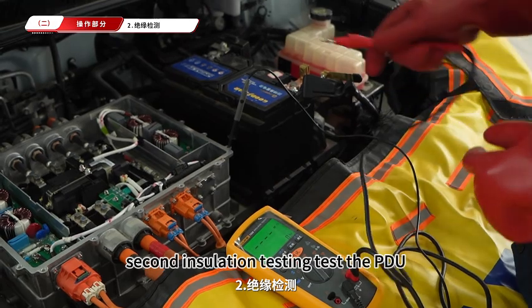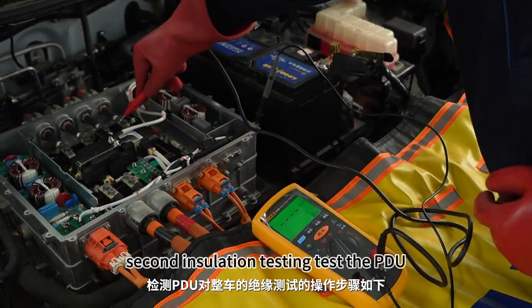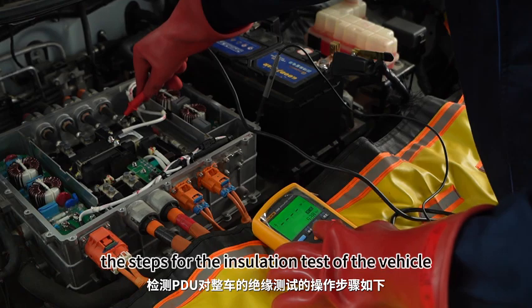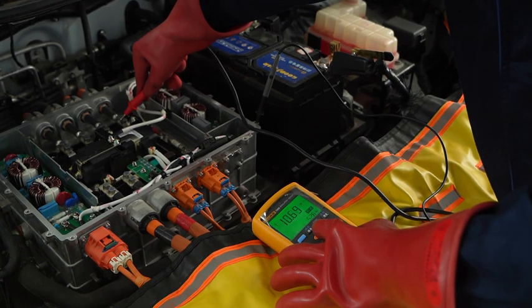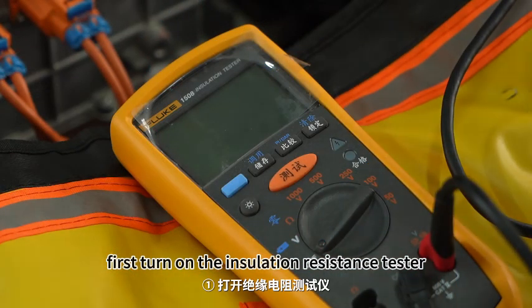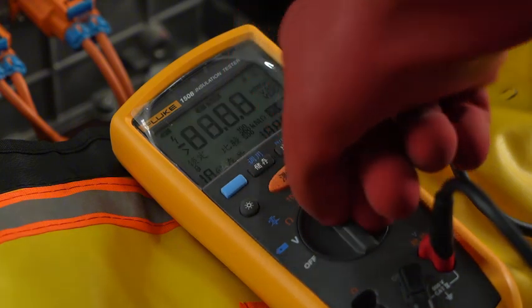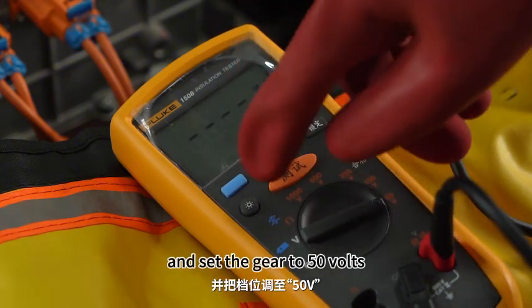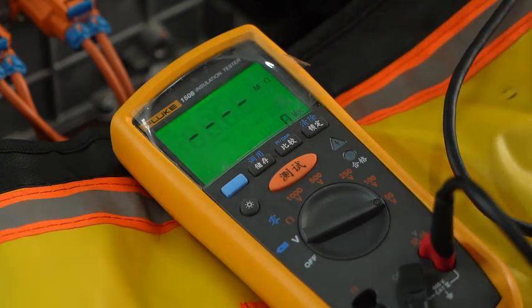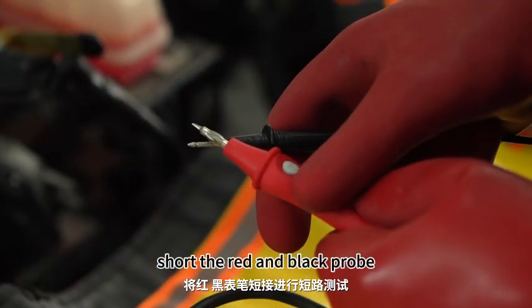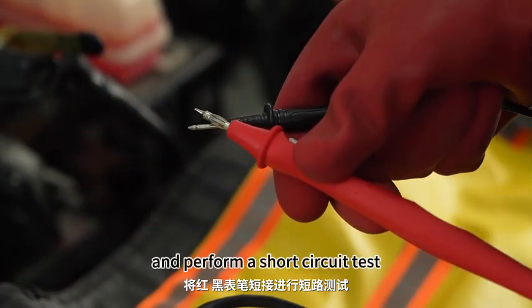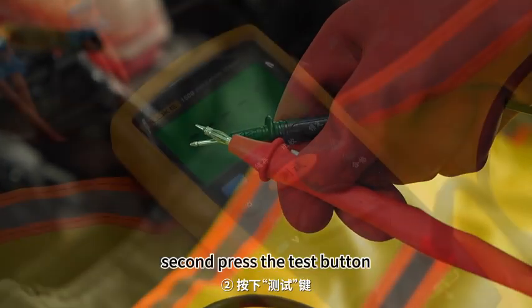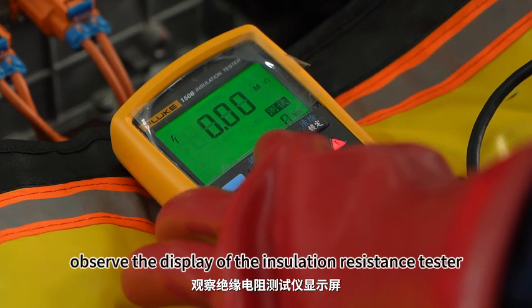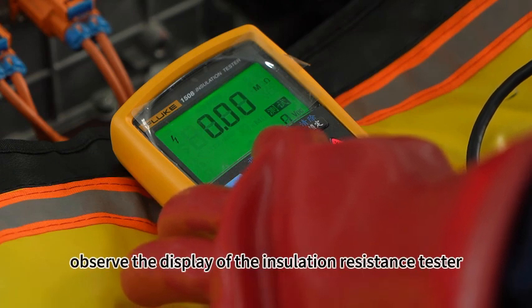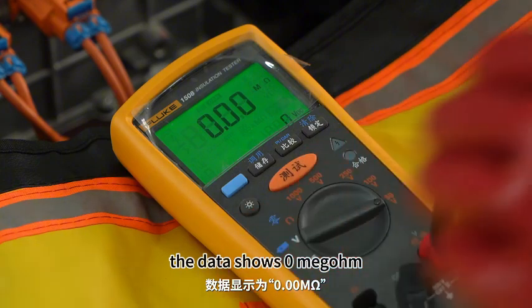Second, insulation testing. The steps for the insulation test of the PDU are as follows. First, turn on the insulation resistance tester and set the gear to 50 volts. Short the red and black probes and perform a short circuit test. Second, press the test button. Observe the display of the insulation resistance tester. The data shows 0 megohm.